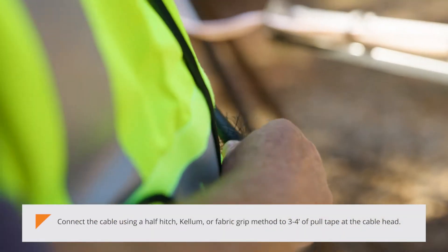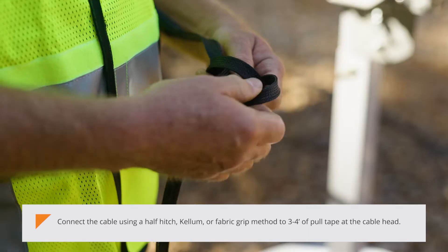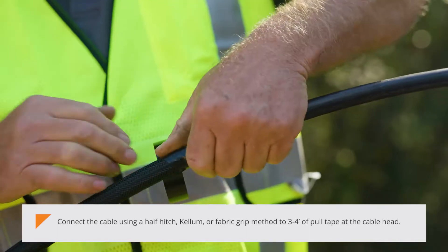Connect the cable using the half hitch, Kellum, or fabric grip method to 3 to 4 feet of pull tape at the cable head.